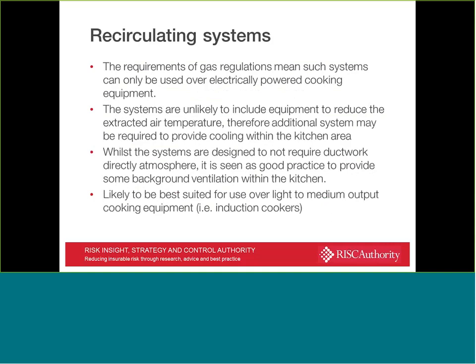In terms of just some caveats associated with these kinds of systems, and I'm not sure we have enough information on them yet really to form an informed view, but these sorts of systems can only be used over electrically powered cooking equipment, not over gas equipment, so that immediately limits their use. They're unlikely to reduce air temperatures, and so there may be a need for additional cooling air to be introduced into the kitchen itself by a separate system.